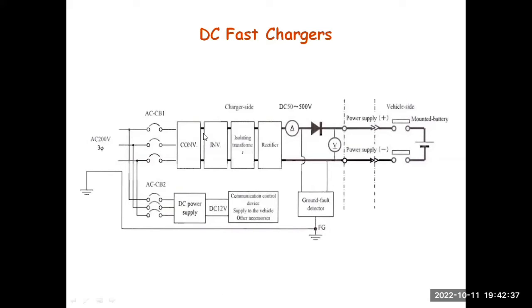Then this front end converter is followed by a DC-DC converter, generally an inverter with isolation, with an isolating transformer and a rectifier. This inverter, isolating transformer and rectifier form a DC-DC converter. Generally the voltage of the active power factor correction converter for a three-phase application will be somewhere around 800 volts. And from 800 volts, it is stepped down using this inverter, isolation transformer and rectifier. So the voltage is converted from this 800 volts to the required output voltage, generally 50 to 500 volts DC.